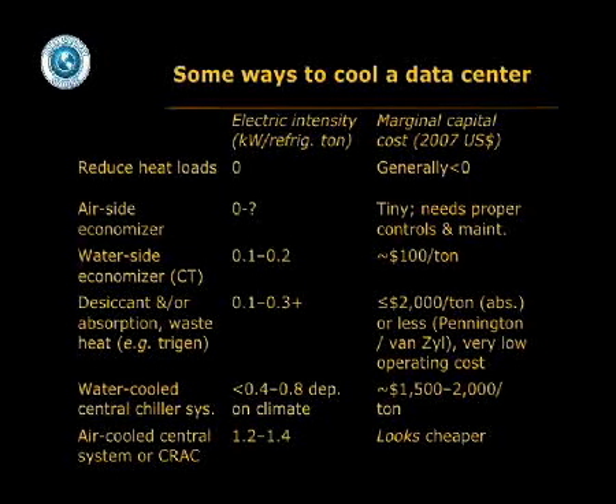Will be down in that range, or if it's not quite as good, maybe a little more, and it'll cost about $100 US per ton. A heat-based system will run somewhere in the same range, maybe a little more, and you can run it off the waste heat of a trigen system. It's dearer. It's up to maybe $2,000 US a ton with absorption, or considerably less with a desiccant-based, desiccant plus direct indirect evap cycle, and very low OPEX. The water-cooled central chiller system might run, depending on climate, 0.4 to 0.8. Around here, roughly 0.6 kilowatt per ton, down approaching 0.5. And it might cost $1.5 or $2,000 US a ton. But what do we all do? We buy air-cooled CRACs, 1.4 if you're lucky kilowatts per ton.